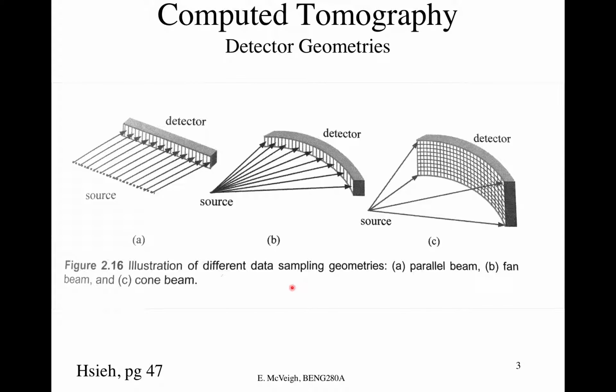So we don't raster a single detector anymore. We have a fixed set of detectors, and in fact, a two-dimensional fixed set of detectors. So it's just like a camera, right? We're going to take a picture that way, and the separation between these elements kind of sets our sampling frequency in the L direction with G(L, theta), right? So that's already set for us by the manufacturer. Unfortunately, we can't dial it and shift them down, shift them up, right?